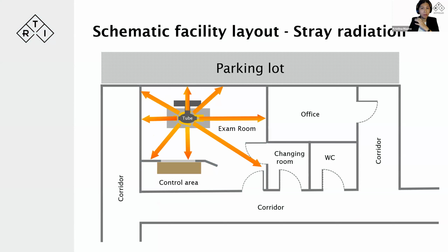So this, of course, can be a concern from a radiation safety point of view, since this may impact adjacent areas around the X-ray room. And both the fluence and the quality of this stray radiation have an angular dependence. And it also does not have the same intensity in all directions. So it's a very special concern, especially in fluoroscopy procedures, which are longer.